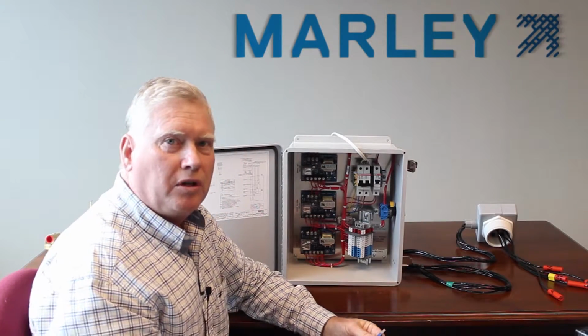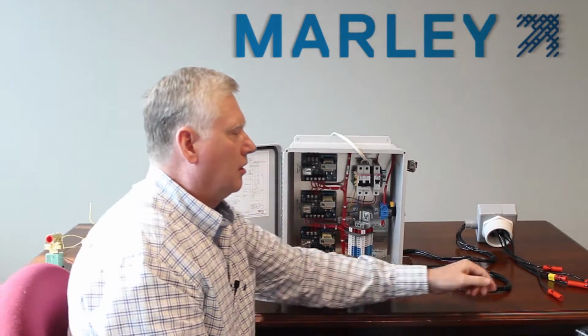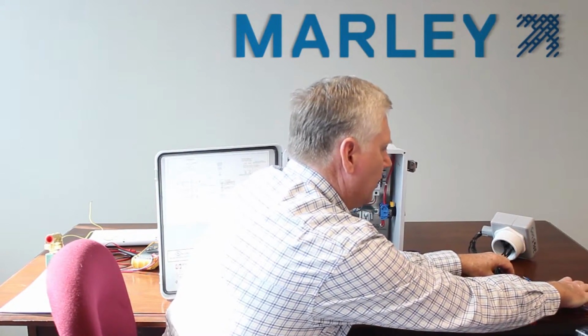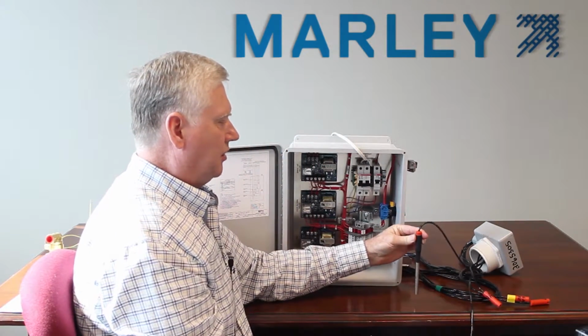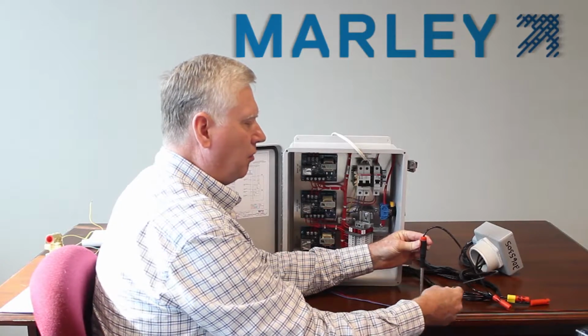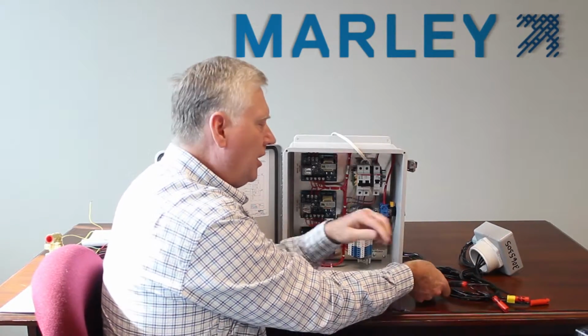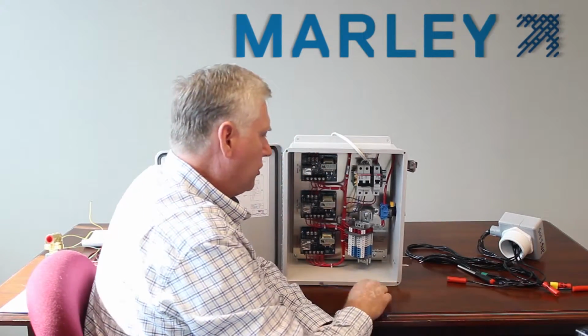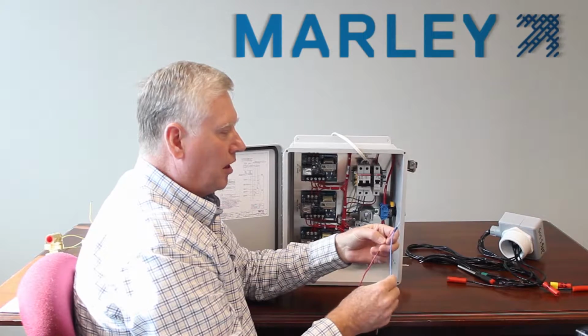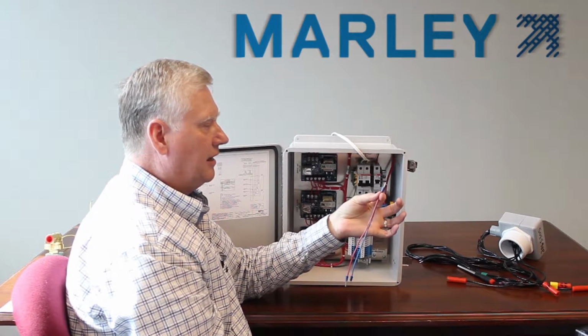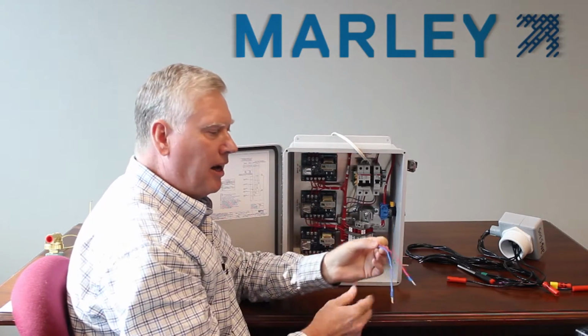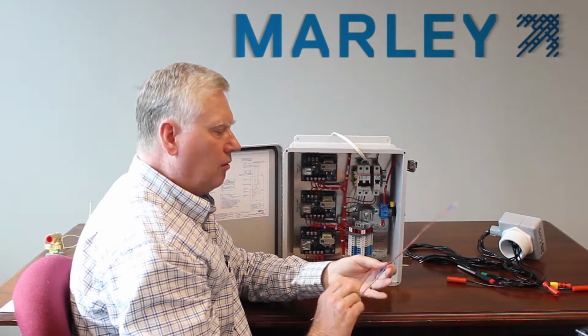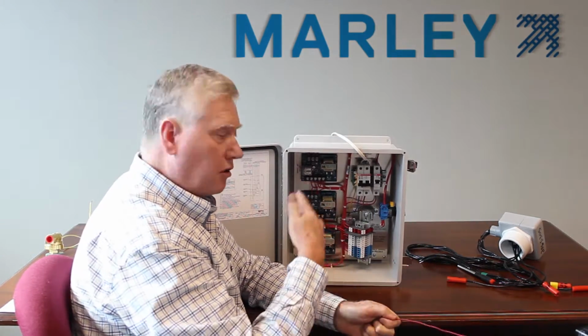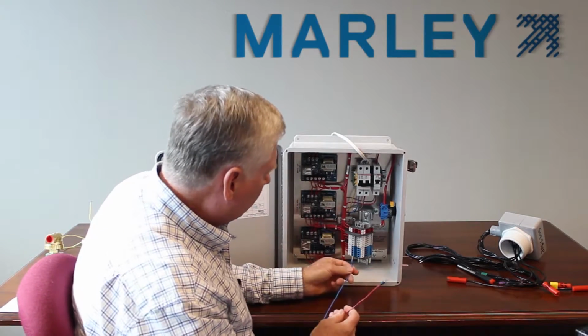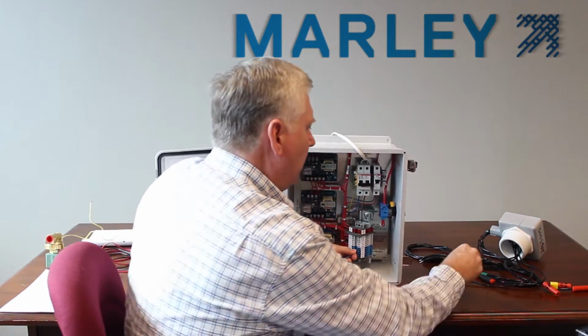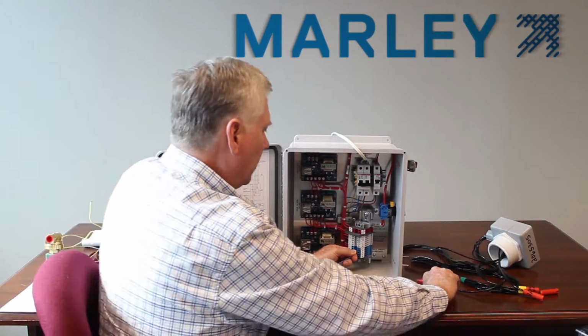If you watched segments 1 and 2, it talks about how conductivity works. Just as a quick review, you have a reference probe that is in the water, and it conducts electricity through the water to the other probes. Well, we're going to do the same thing and not use the probes. Instead, we're just going to use a wire jumper. This particular wire jumper that I made, I used 2 wires and tied the ends together so I can check all the cards, including the makeup, which actually uses 2 probes. But for right now, we're just going to test one of the cards. We're going to take this card by card. So you need one in on number 13, which represents the reference probe that is in the water.